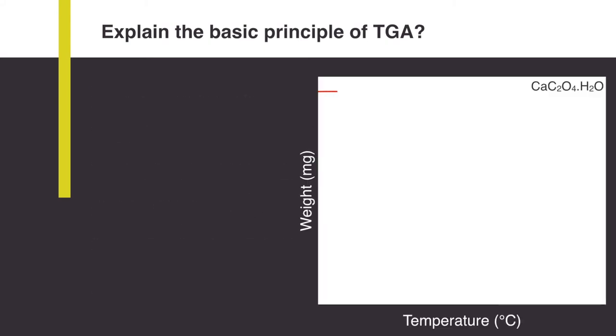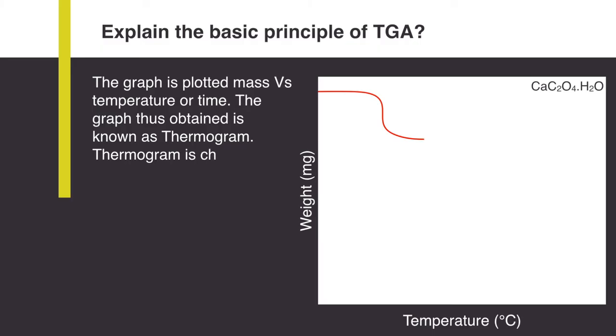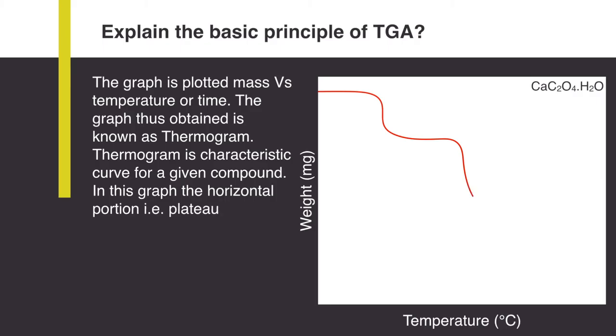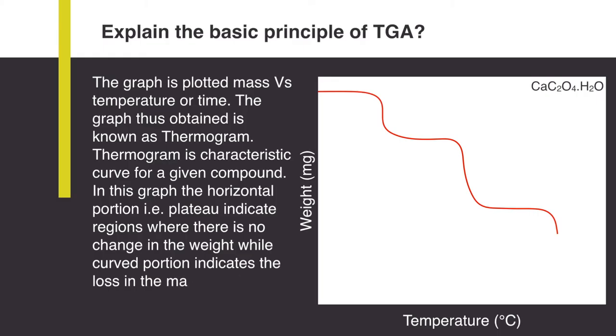The graph of mass versus temperature or time is recorded. The graph thus obtained is known as a thermogram. A thermogram is a characteristic curve for a given compound. In this graph, the horizontal portion or plateau indicates regions where there is no change in weight, while the curved portion indicates loss in mass. The heating temperature varies from ambient to 1500 degrees Celsius.